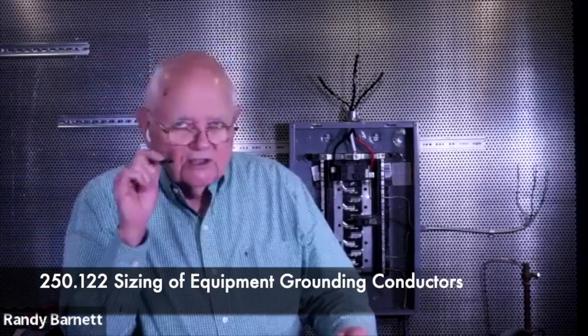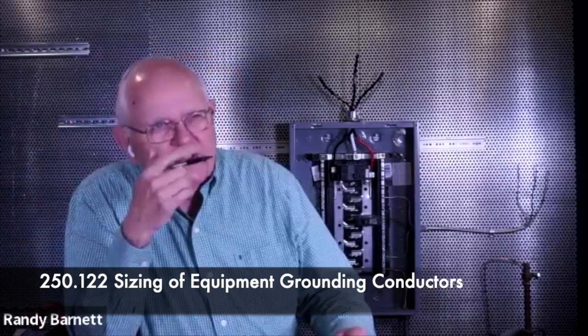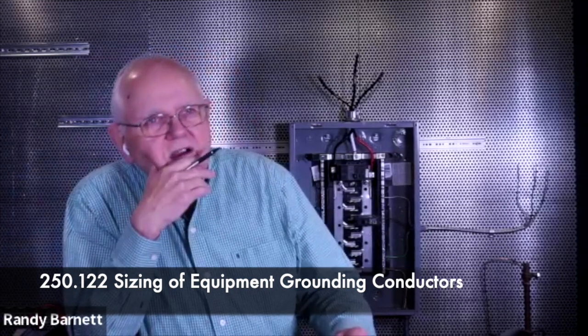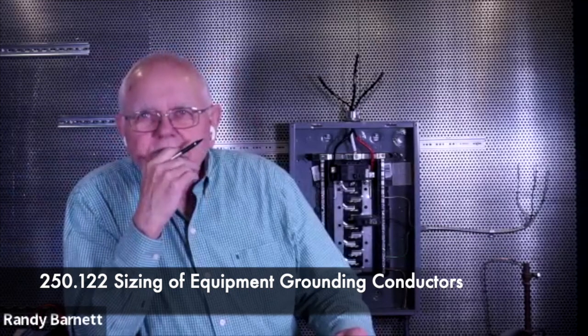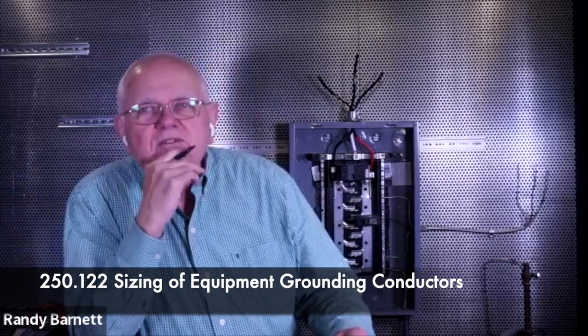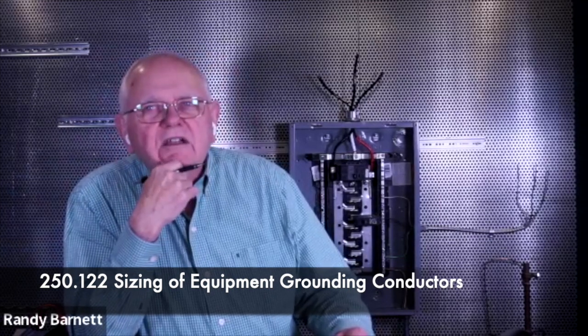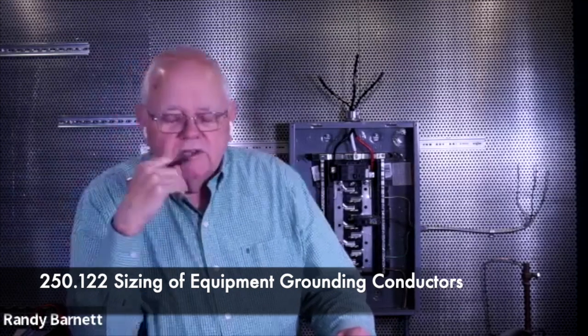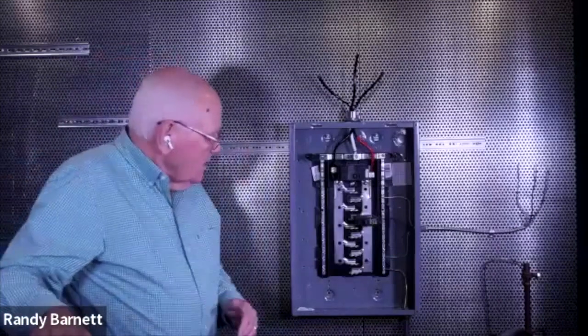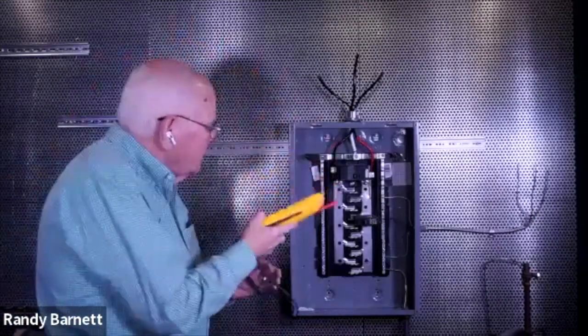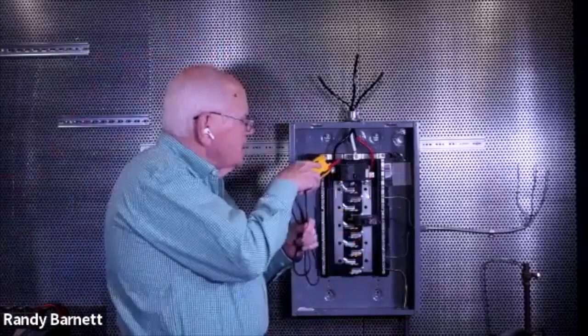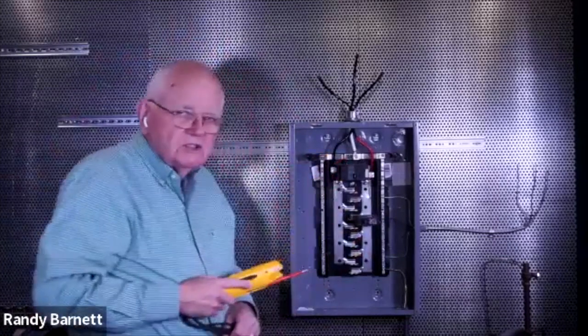It also talks about, in a case where maybe you had to upsize the phase conductors because of voltage drop, a need as well to upsize the equipment grounding conductor, something that's easy to miss when we're doing installation work. So we've talked a lot about the conductors. Let's talk about this jumper up here, the main bonding jumper.